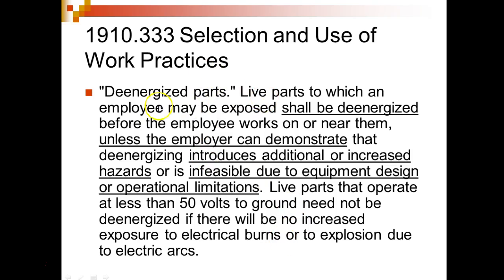333 says live parts to which employees may be exposed shall be de-energized before the employee works on or near them, unless the employer can demonstrate that de-energizing introduces additional or increased hazards, or it is infeasible due to equipment design and operational limitations. Live parts that operate at less than 50 volts to ground need not be de-energized if there will be no increased exposure to electrical burns due to explosions or electrical arcs.